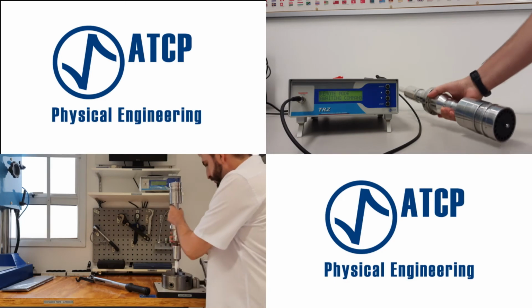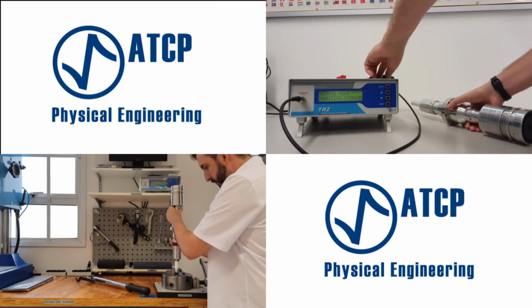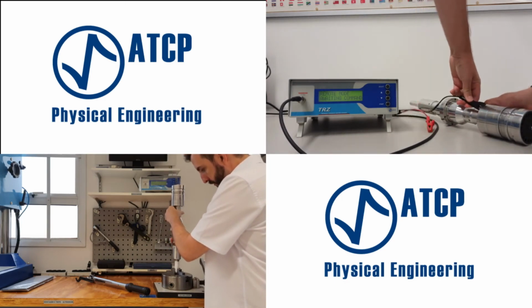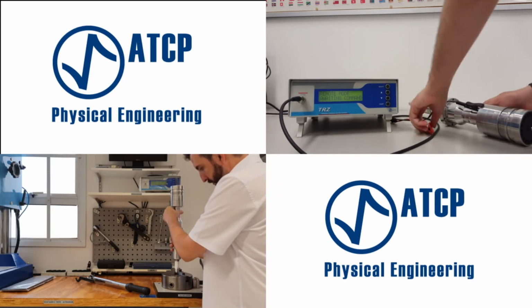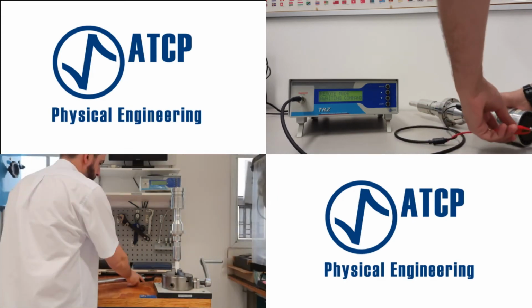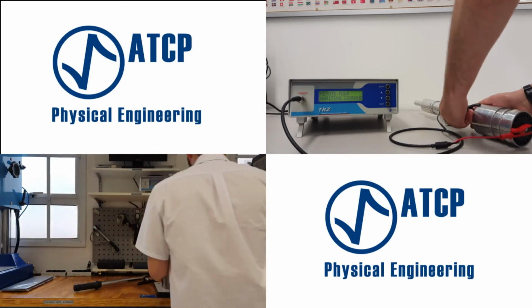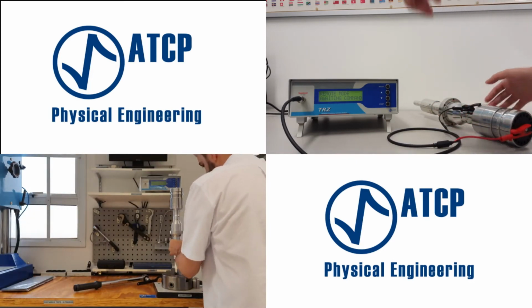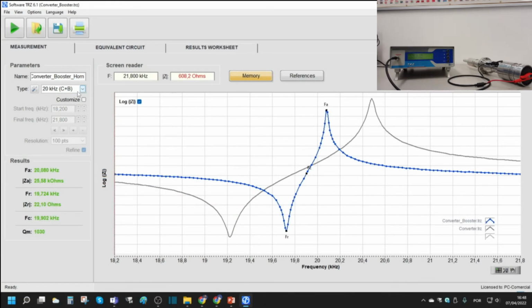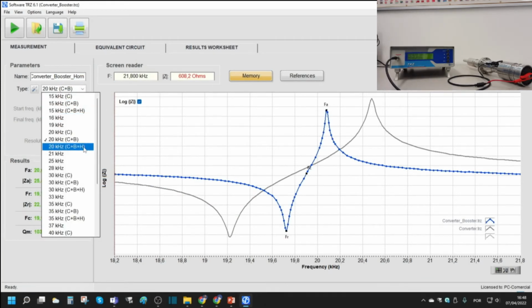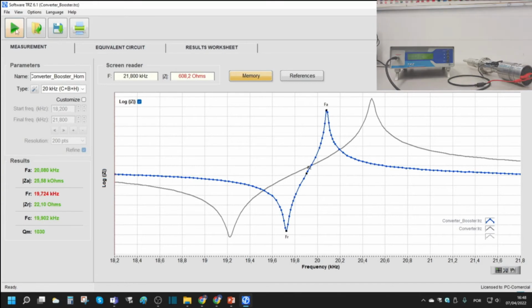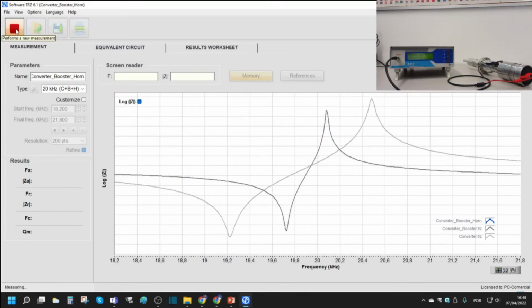To test the horn, the procedure is again similar to the converter test. First, assemble the complete stack and connect the converter to the TRZ clips. Remember, the converter and booster must be in good condition to test the horn. Select C plus B plus H in the software. Finally, press play button to perform the measurement.